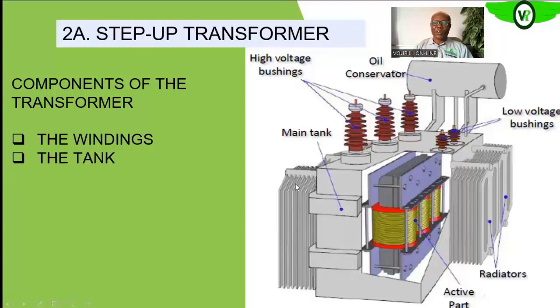The other component that we want to look at now is the tank, and this is the tank. The transformer tank is what is housing the main winding. The winding and the core are placed inside the transformer tank, as you can see. It is also the part that houses the insulating oil, the oil that helps to cool the transformer winding.